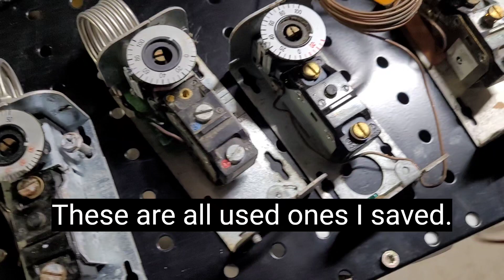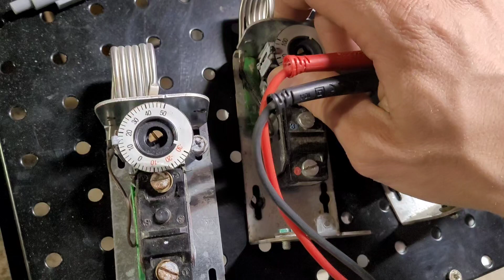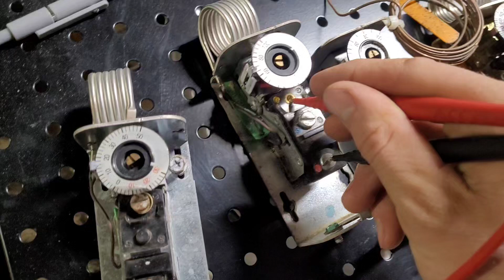Then we have this one here. You can see it has 3 contacts: yellow, blue, and red. Between yellow and red we have continuity right now because it's turned down, and when you turn it up, it will open that contact—see that? But it'll close this contact here. So when you turn it back this way, it opens that contact and closes this one. So you can use this one to either bring on a heater or bring on air conditioning or a cooler. This is the type we need.